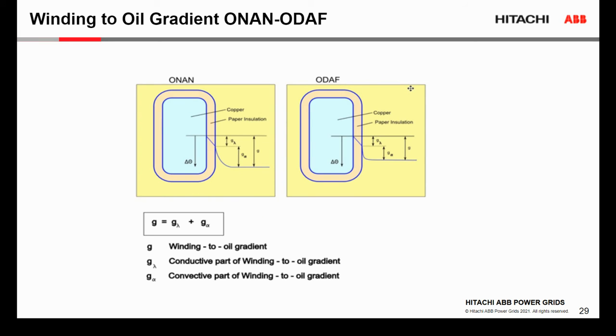Now, a little bit more on why we see a significant difference in the gradient for transformers with natural oil circulation and in transformers with directed oil into the windings. The gradient between the winding and the adjacent oil has two components. First is the conductive part. This conductive part is driven usually by the thickness of the insulation on the conductor, and it is pretty much the same as we see for ONAN and ODAF cooling.